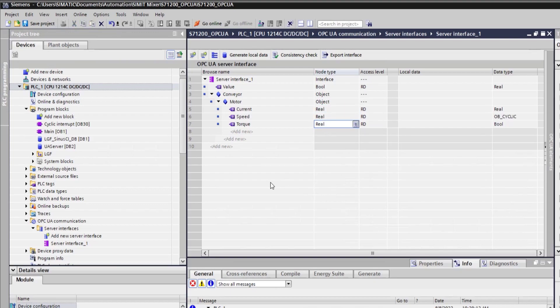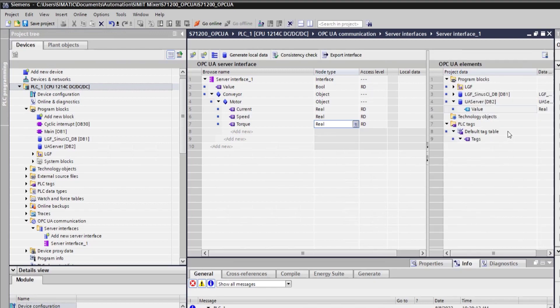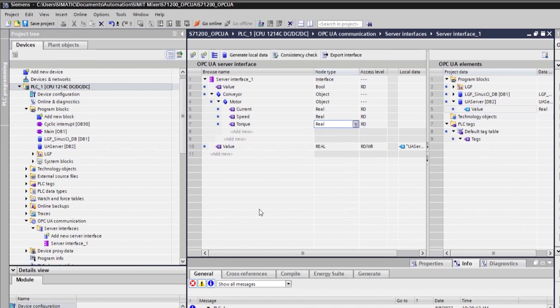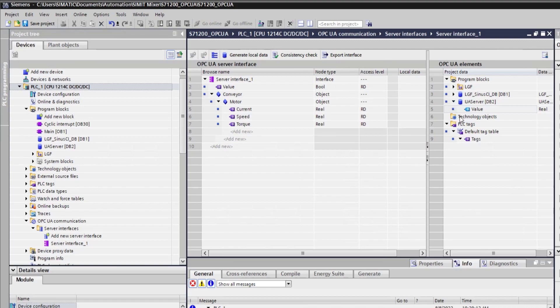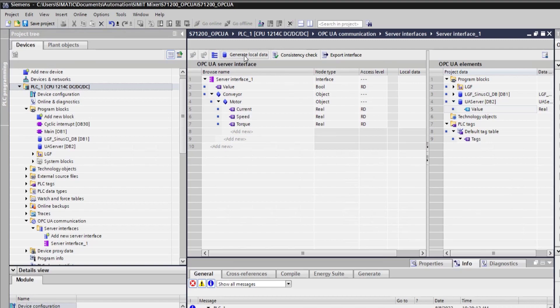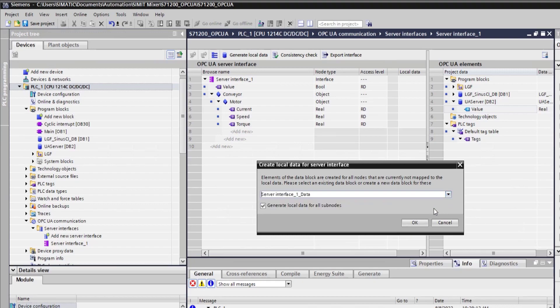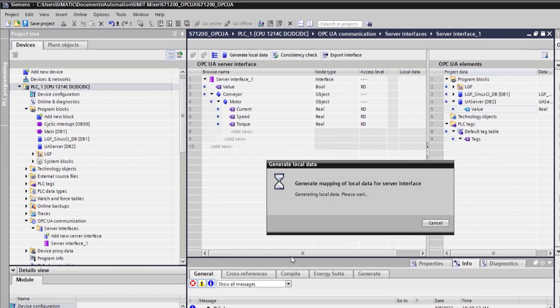So we can actually prepare it like this. You can mix and match. So you can actually drag and drop this value here. And that's fine. But what you can do, once you created this server interface, you prepared it, you can use generate local data. So this is going to look at this. And basically, for the variables that are not mapped yet, it's going to create you a nice new data block. So a new general data block, server interface data, you can change it. And as you can see, it created me a data block with all these things here.